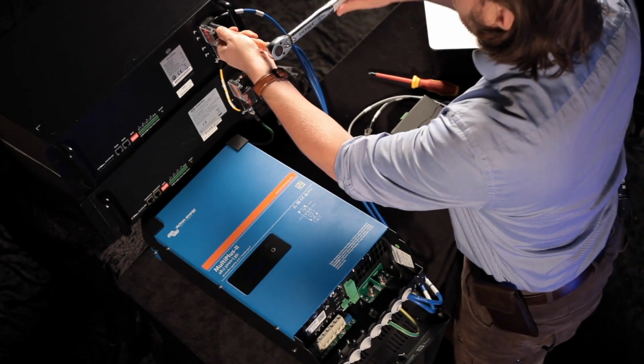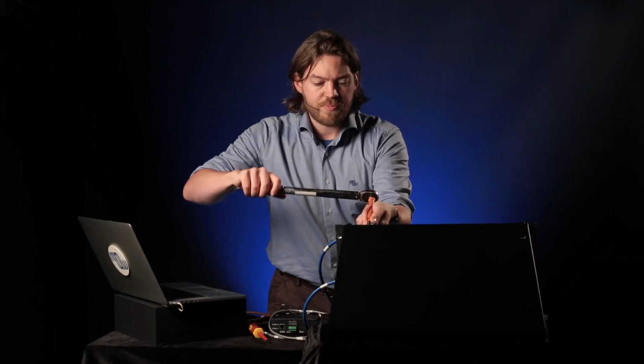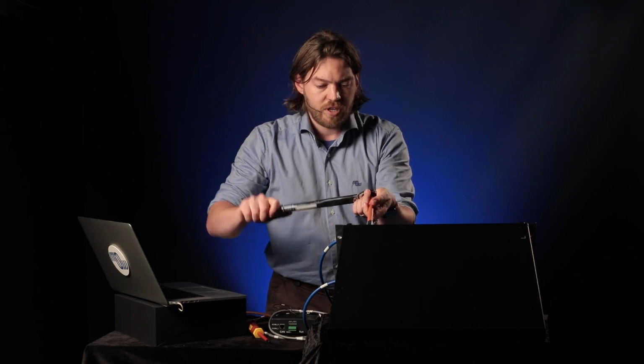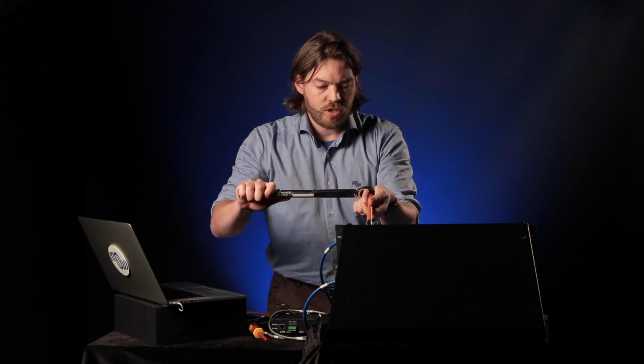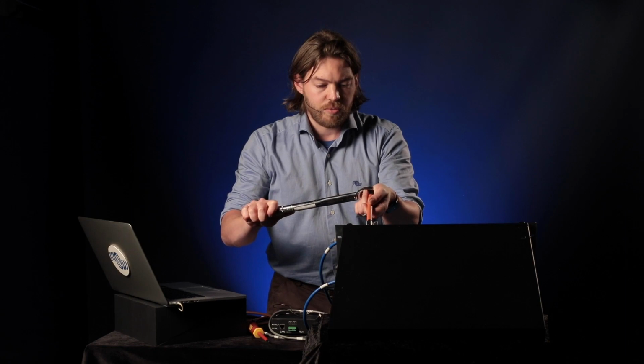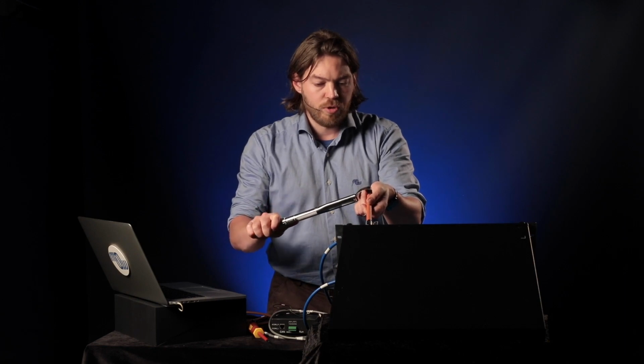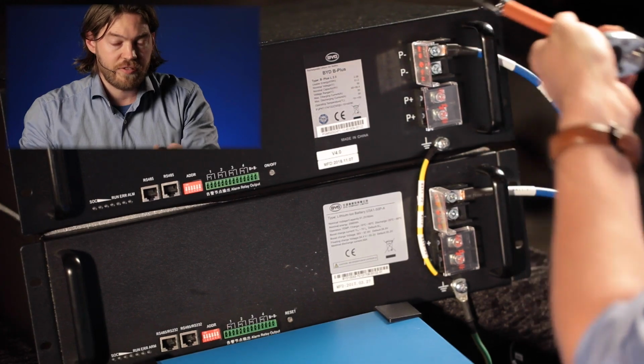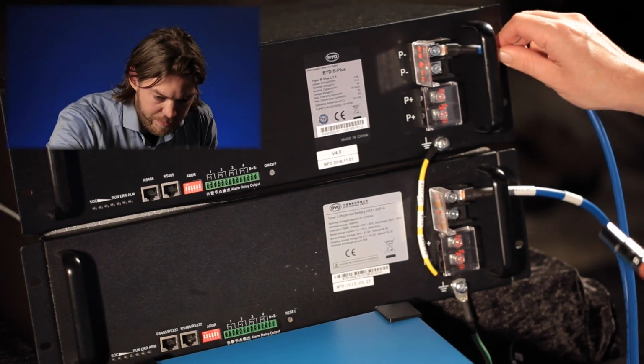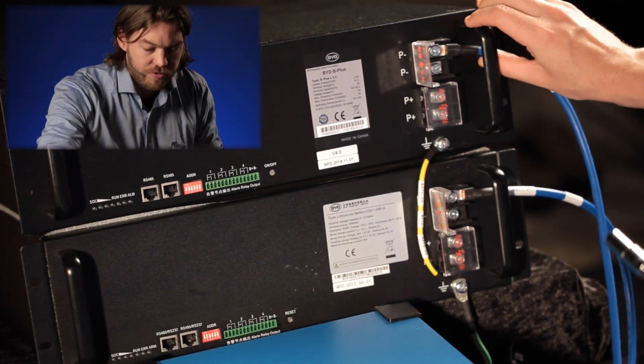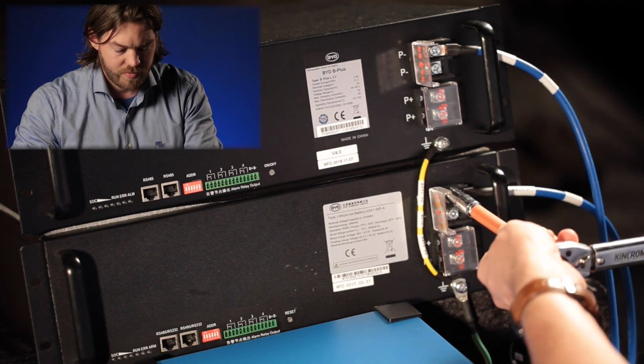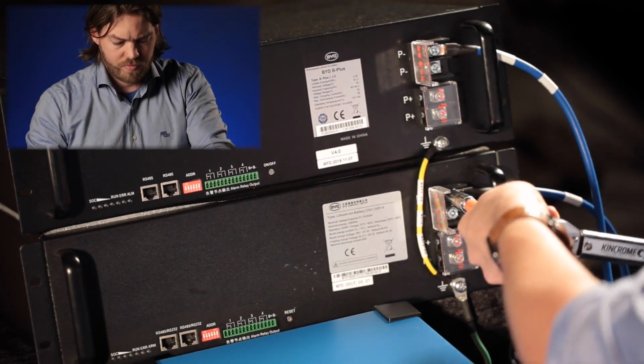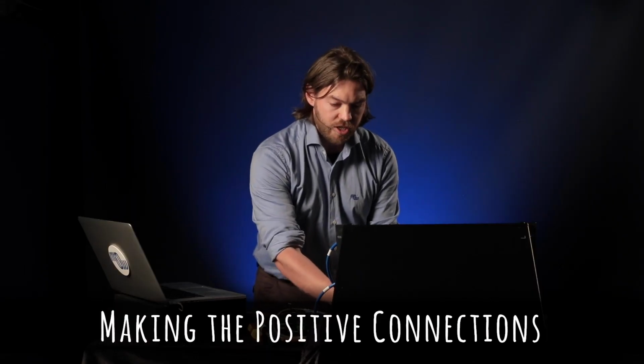Now, the BYDs have a specified torque, but if you don't have a torque wrench, you can also tell just by the way the battery terminal moves where they're tight enough. So once you tighten it up and that battery terminal itself as a whole begins to move, that's tight. Now we'll move on to the positive connections.